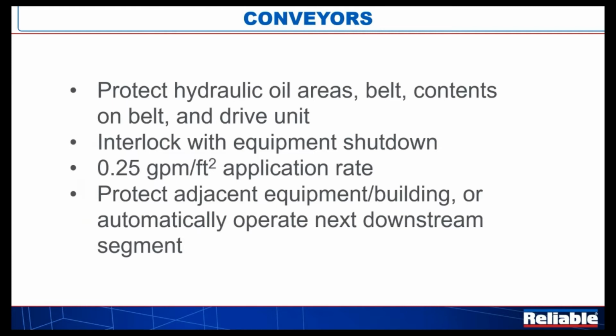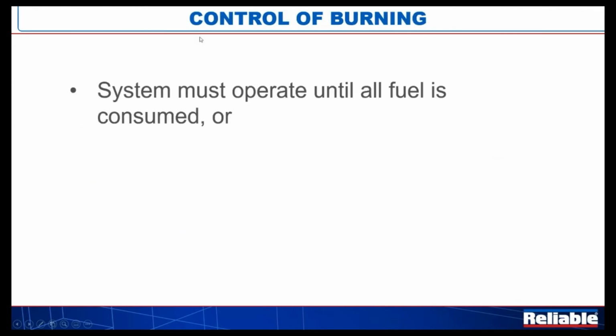And then in probably more like an and/or situation, you want to automatically operate the next downstream segment of the protection. So if your system is zoned out, maybe it's by footage or whatever, when the fire sprinkler system operates, wherever that material is moving to, that next zone downstream, we want to operate that system as well. So you need to be aware that you may have, much in the case of an aircraft hangar, more than one zone anticipated to operate at the same time, which obviously has an effect on your water supply and duration and things like that. So this next section is what they call control of burning.